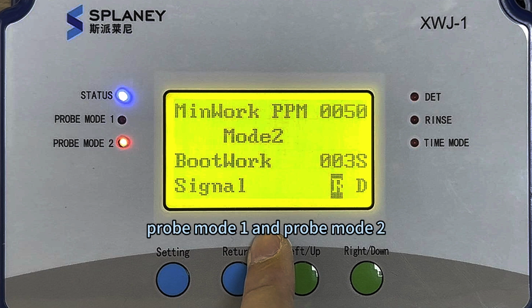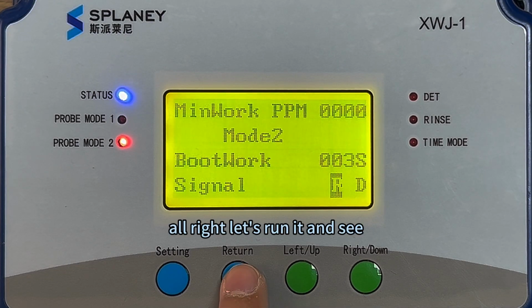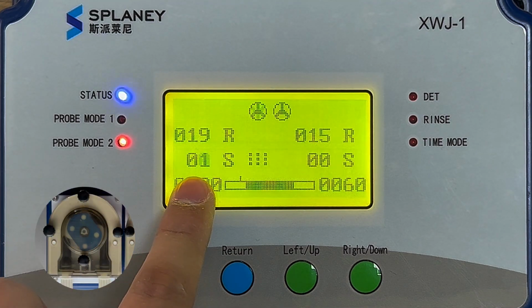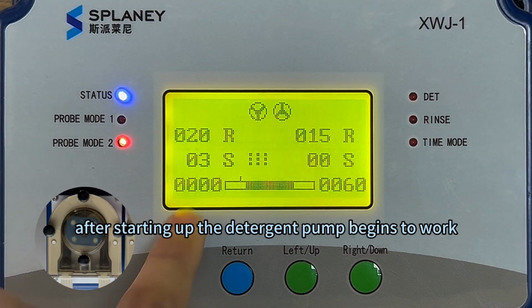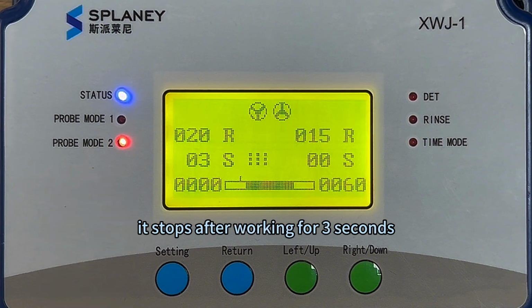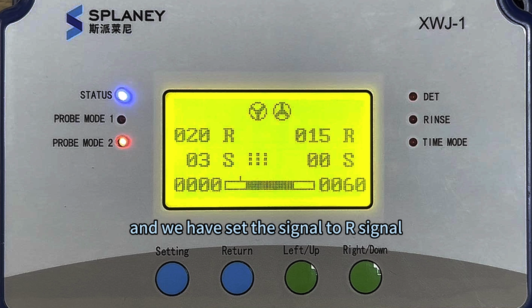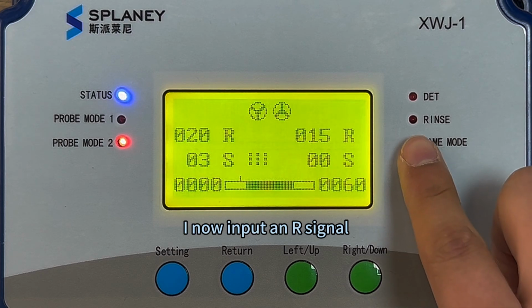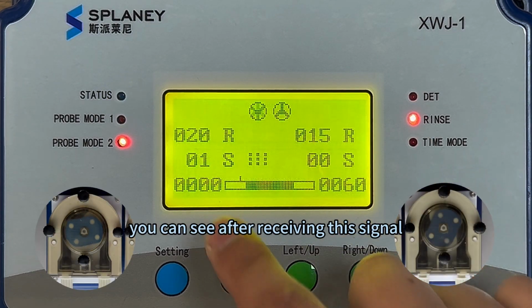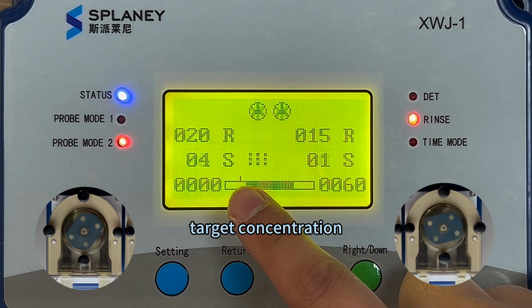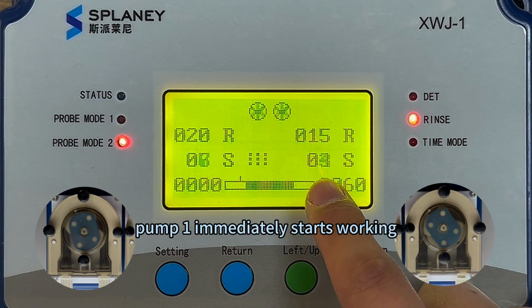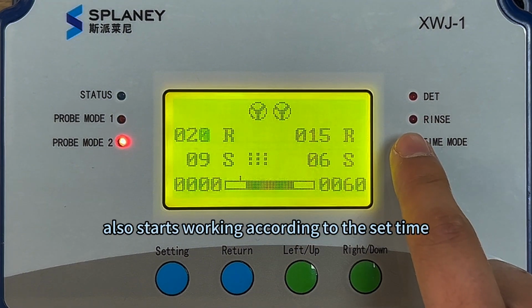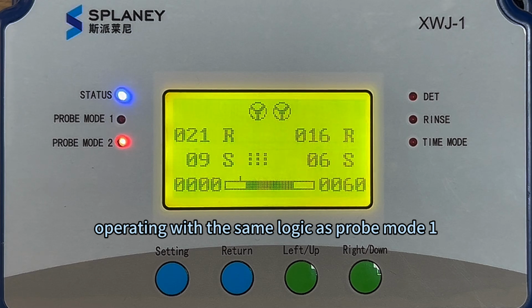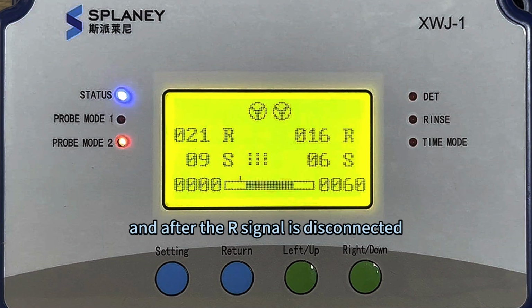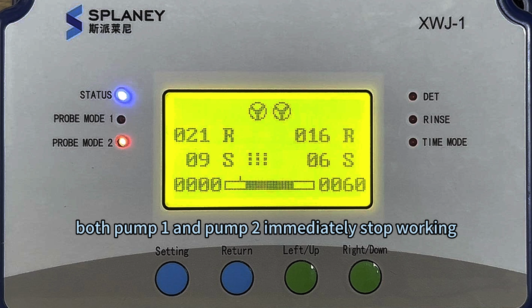All right, let's run it and see. You can see, after starting up, the detergent pump begins to work. It stops after working for 3 seconds, and we have set the signal to R signal. Before receiving the R signal, neither of our 2 pumps will work. I now input an R signal. You can see after receiving the signal, since the concentration does not reach the set target concentration, pump 1 immediately starts working, and pump 2 also starts working according to the set time, operating with the same logic as probe mode 1. And after the R signal is disconnected, both pump 1 and pump 2 immediately stop working.